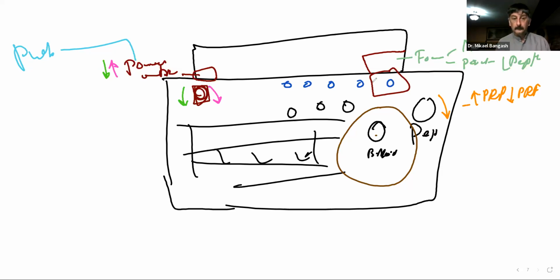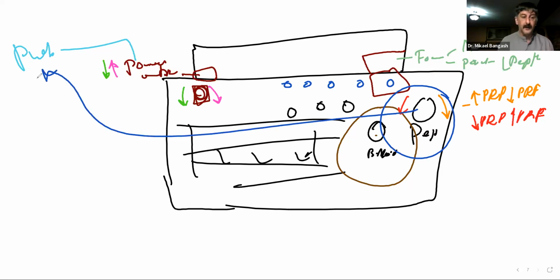So decreasing the depth will decrease the PRP or increase the PRF. Twisting and turning the depth knob here is going to convey the respective signals, a command to the pulser, saying we increase the depth, increase the PRP. And the greater the PRP, the lower will be the PRF, and vice versa.